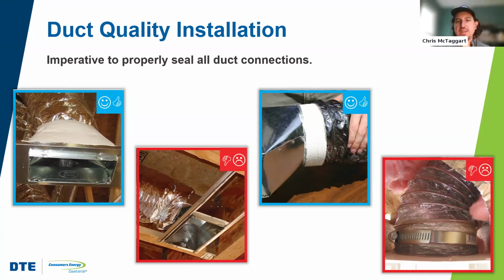The connections between the fittings or seams of boots need to be taken into consideration. Then finally, you have to seal the boot to drywall or boot to finish floor connection, because that's a place where you can have a lot of leakage as well. Someone mentioned here, Ryan, not 4, 8, or 12% leakage verbally stated by Chris, but rather 4, 8, or 12 CFM 25, which is much lower.